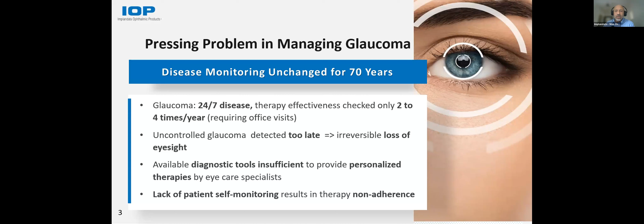So to overcome this problem, we have developed the IMID system, which is a combination of tiny implantable microsensors, which are today either placed in combination with glaucoma surgery or in combination with cataract surgery. In the next step, it will also be injected in an in-office procedure. These sensors are safely placed inside the patient's eye and telemetrically powered by RFID. So patients really don't feel the sensor, and it does not do any harm to the patient. It only measures when the measurement is actuated from the outside. So you can do it on demand with that handheld, but we can also do fully automated measurements. For example, you can also obtain measurements during the night. So it's really like a Holter monitor for the eye.